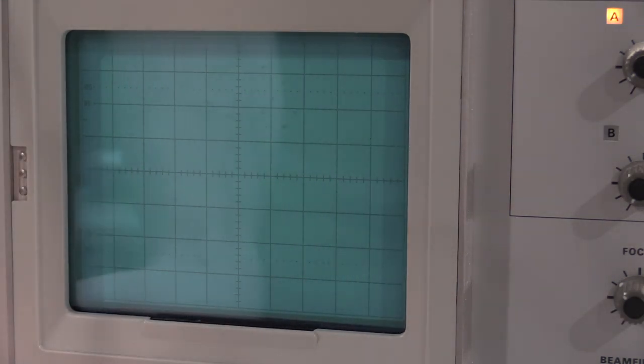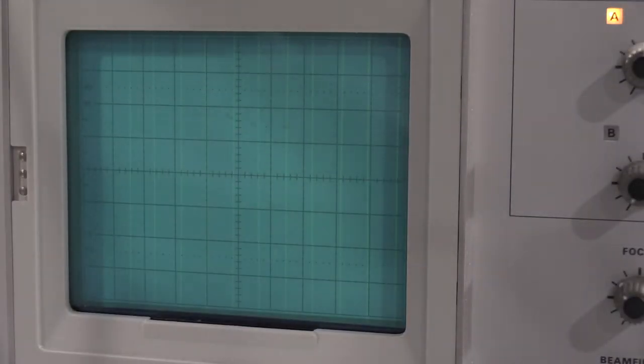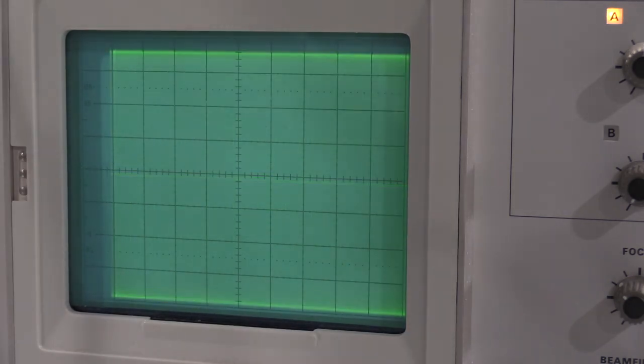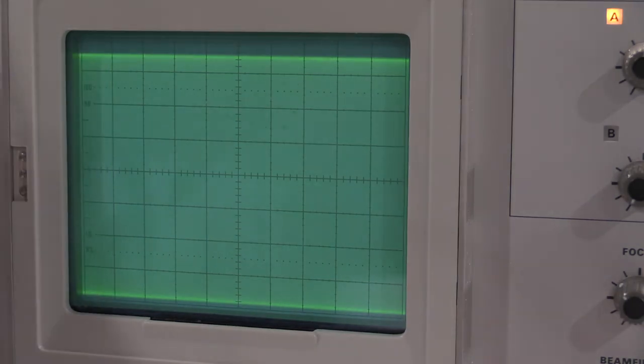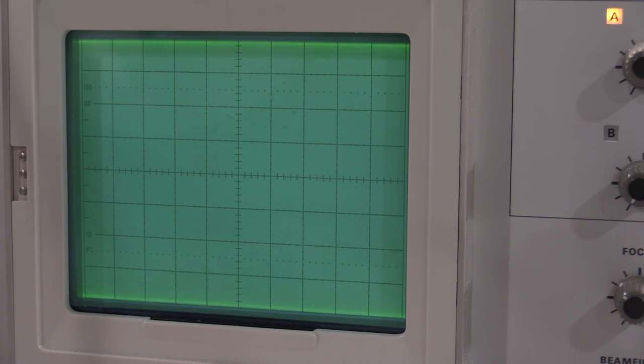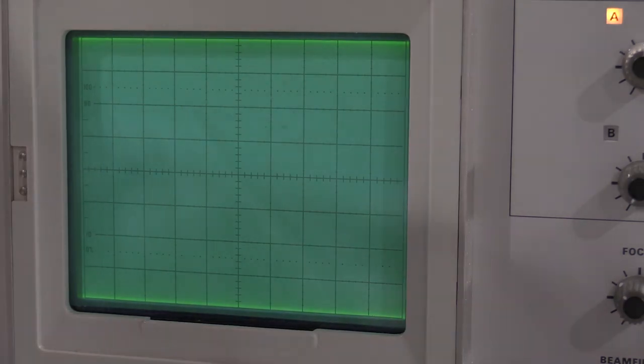Okay, I'm getting everything set up for the common mode rejection ratio. We're on channel 1. Give me some trace. Ooh, lots of signal. Roll this down. So it wants 50 megahertz. There's 50. And we want 8 divisions of display. There's pretty much 8 divisions.